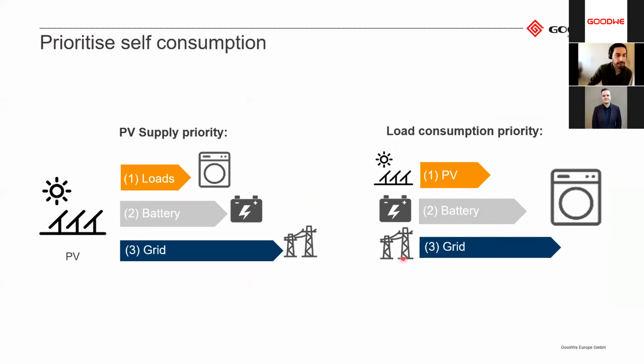Here you see how the energy flows from the PV and how the loads receive energy. There are different ways to set this up. You have different settings in the commissioning app, but in the general settings, the inverter always tries to prioritize that the energy from the PV first goes to the loads to cover them. And if there's any energy left over, then it charges the battery. And if the loads are covered and the battery is full, then you export the rest to the grid, in case you don't have an export limit set up, and then it will just reduce the PV power. And for the loads, it will always try to first take energy from the PV, then the battery, and then lastly the grid.